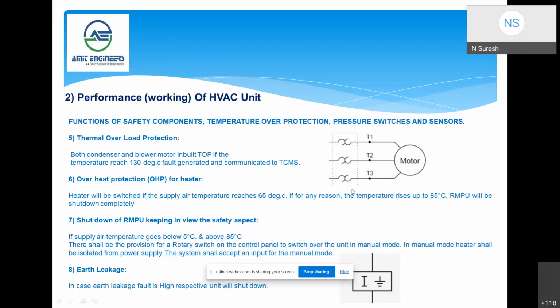As well as that, if the supply air temperature goes on the lower side, below 5 degrees, in that case also it will switch off the compressor. Since supply air temperature below 5 degrees is not good for humans, it will give a cold shock. That's why this logic is there.